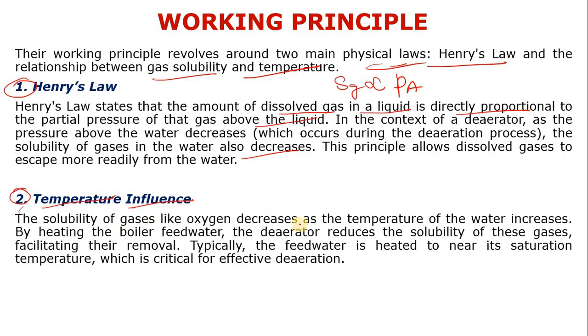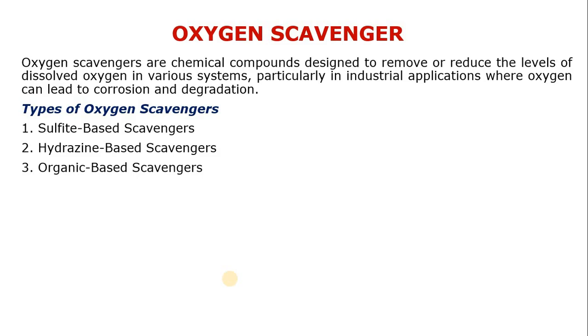The second principle is temperature influence: the solubility of gases like oxygen decreases as the temperature of water increases. By heating the boiler feed water, the de-aerator reduces the solubility of these gases, facilitating their removal. Typically the feed water is heated to near its saturation temperature, which is critical for effective de-aeration. As you increase the temperature, solubility decreases, and the dissolved gases are removed.